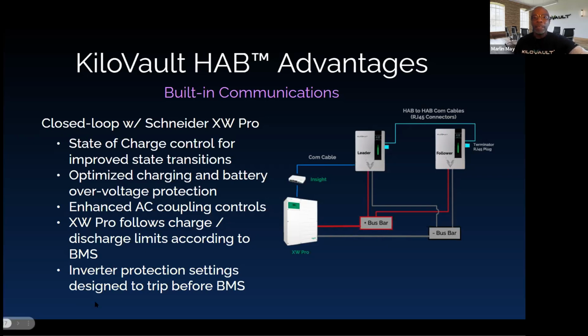Along the same lines, the inverter protection settings are designed to trip before the BMS starts to issue commands to protect the battery itself, so that the protection settings you'd normally program into your XW Pro—your high voltage disconnect, low voltage disconnect, current disconnects, and so on—are actually taken care of by the HAB.